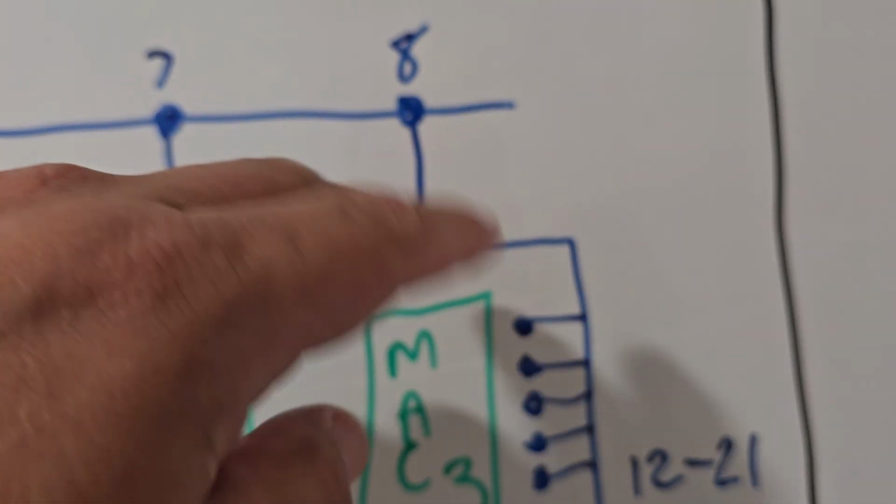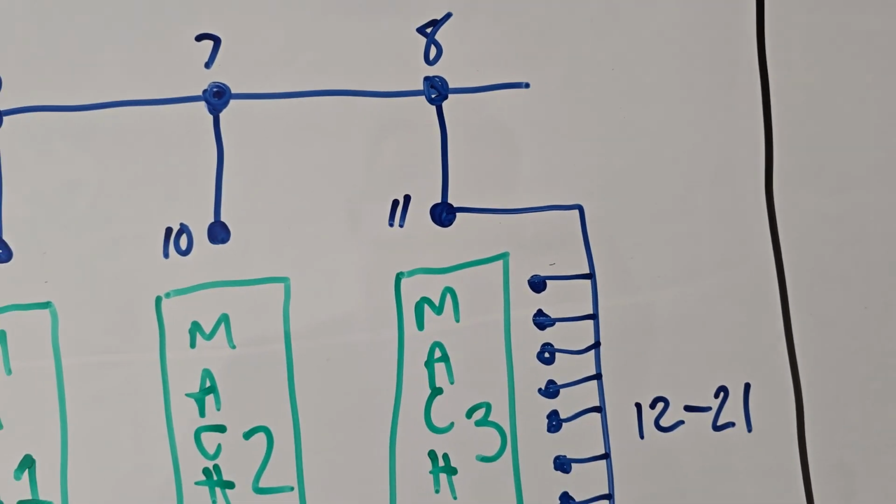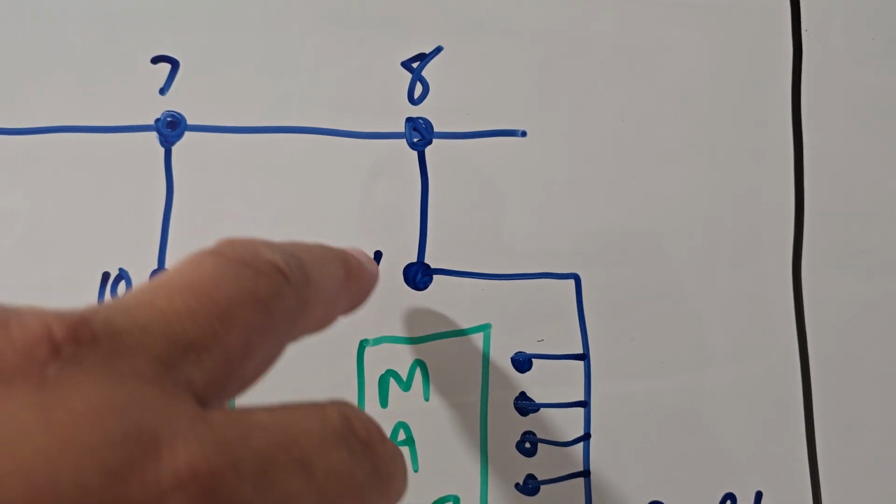So once we verified with data collection that pressure was actually dropping, the question is, is there a problem, or does it think there's a problem? When we talk about sensors and alarms, when the alarm goes off, we have to ask, is it real or does it think it's real? So we have to verify, is that pressure reading what it thinks it's reading? That was done. So now we know that we're having pressure drop here, and here.